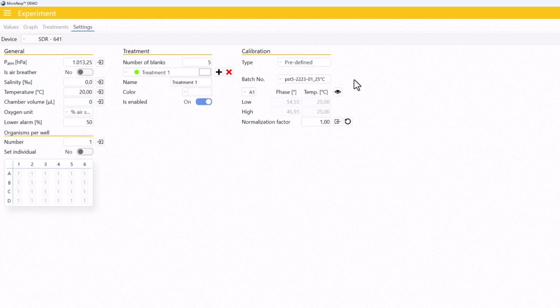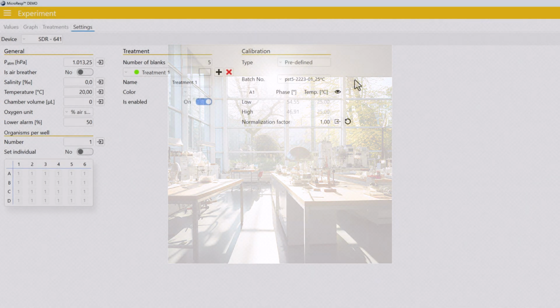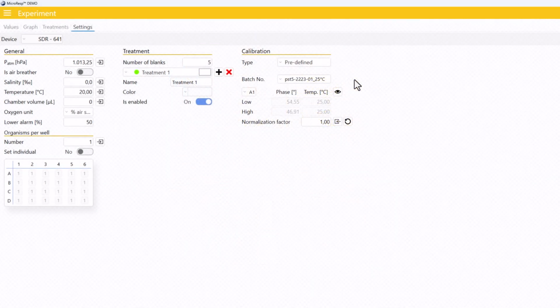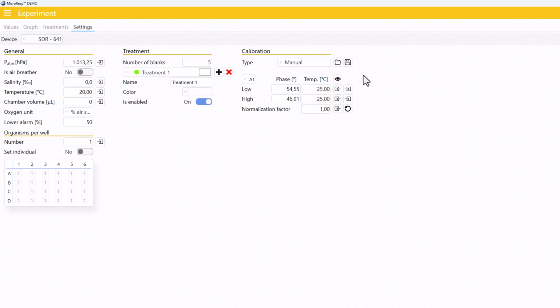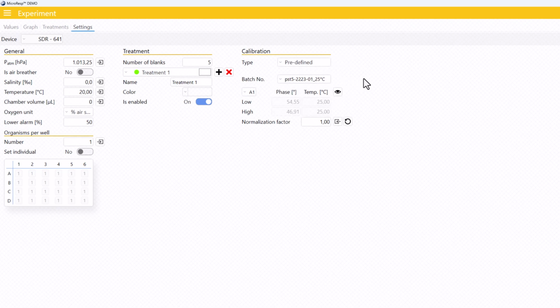However, optical oxygen sensors can bleach over time, especially when exposed to UV light, resulting in a signal drift, which will give inaccurate oxygen readings. This is why we highly recommend performing your own manual calibrations for experimental trials instead of using factory calibration data that should only be used for preliminary trials.